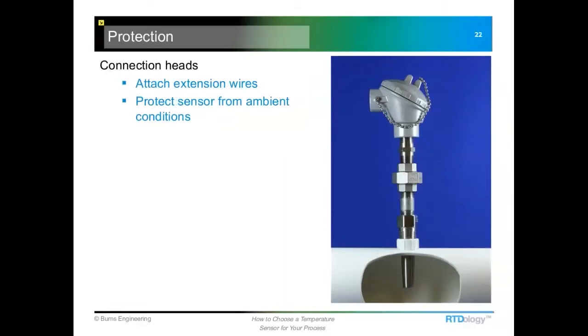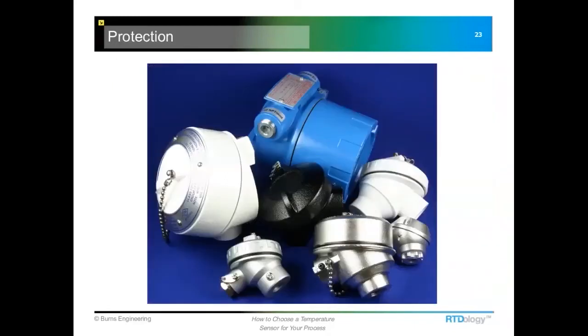So the purpose of the connection head is to either house a transmitter or a terminal block, so we've got some place to land the wires from the RTD. It also protects it from moisture, damage from dust and whatever else might be going on within the factory. And there's just a whole variety of heads that are available. Some are explosion proof. Different materials are aluminum, plastic, stainless steel, and different coatings. We show some here, like this one's got an epoxy paint on it.